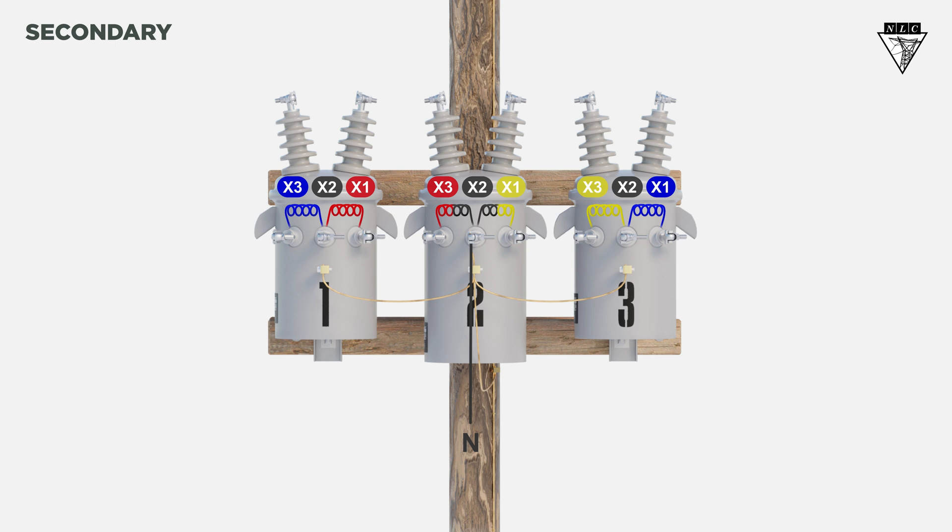Next, connect the X1 of the first transformer to the X3 of the second transformer. Connect the X1 of the second transformer to the X3 of the third transformer. Then connect the X1 of the third transformer to the X3 of the first transformer.